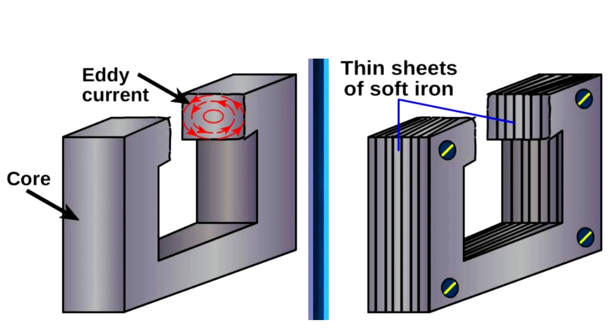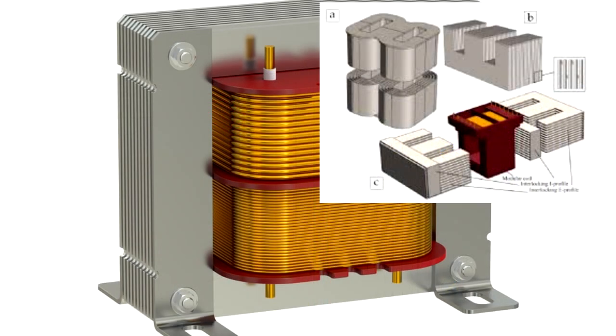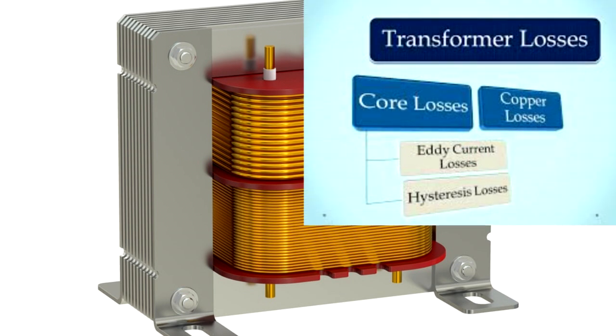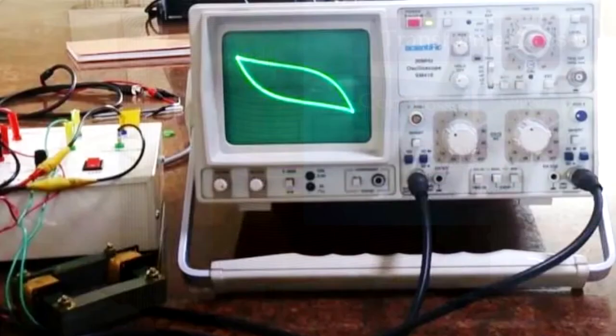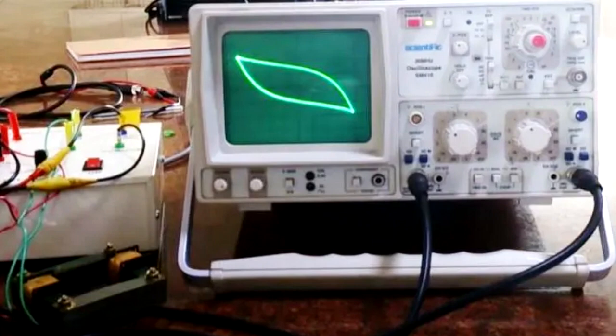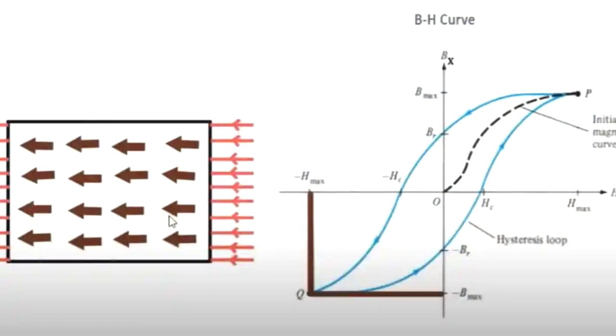And conventional transformers have a laminated core. The reason that they have a laminated core is to make the electrical resistance of that core very high. So that's to reduce the circulating currents and reduce the eddy current losses. The final type of transformer loss that I'm going to talk about today is hysteresis loss, and this is another of our iron losses. So at this point in the proceedings is where I would normally present a hysteresis graph, and I believe the purpose of this hysteresis graph is to show that the magnetic material in the transformer needs slightly more energy to reverse its direction of magnetisation. But I have to say personally I've never really understood this graph very well.